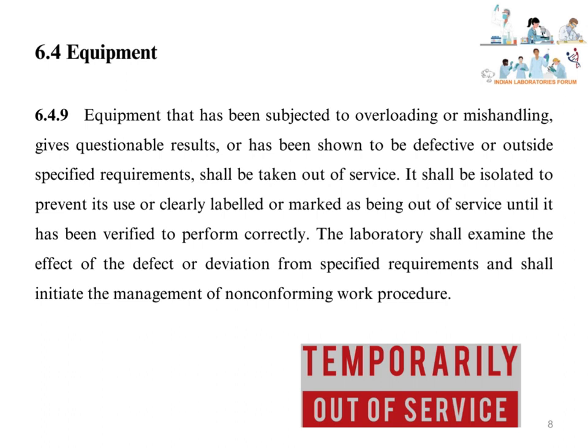Equipment that has been subjected to overloading or mishandling, gives questionable results, or has been shown to be defective or outside specified requirements, shall be taken out of service. Malfunctional equipment should be removed from the point of use or labeled to not be used. It shall be isolated or clearly marked as out of service until verified to perform correctly. The laboratory shall examine the effect of the defect and shall initiate the management of non-conforming work procedure, including impact assessment on previous analyses and appropriate CAPA through the non-conformance procedure.